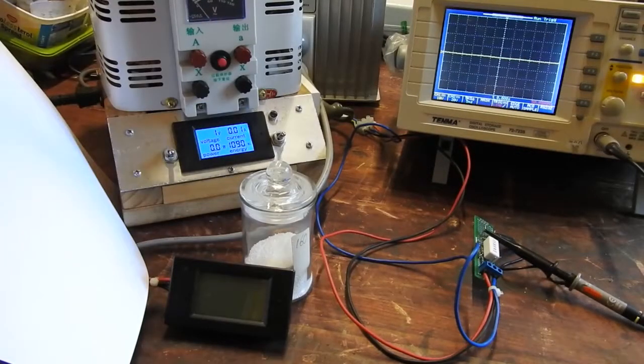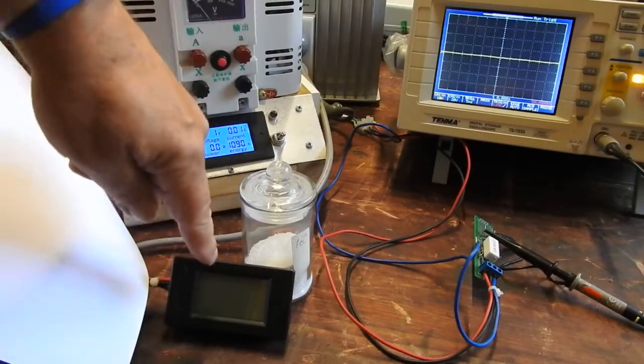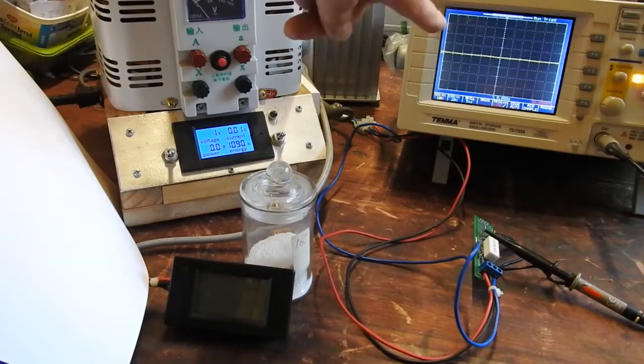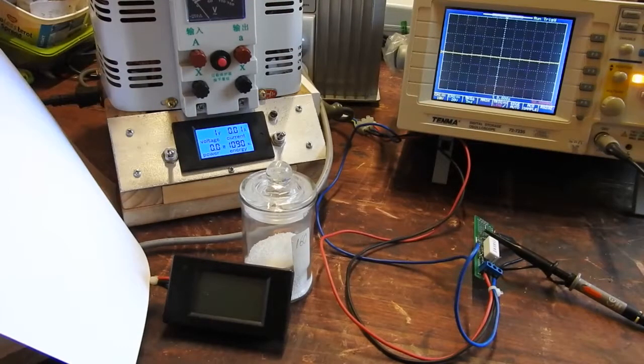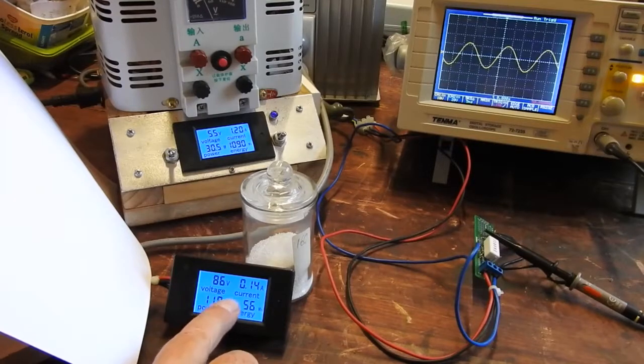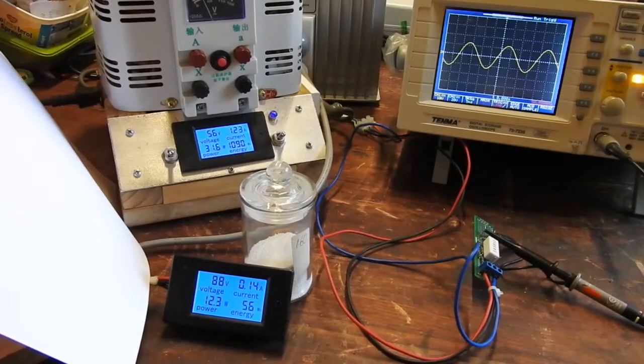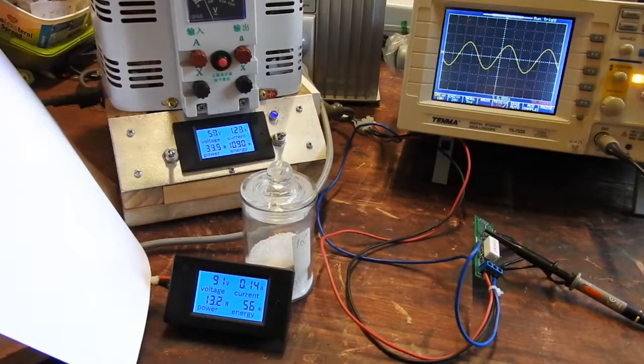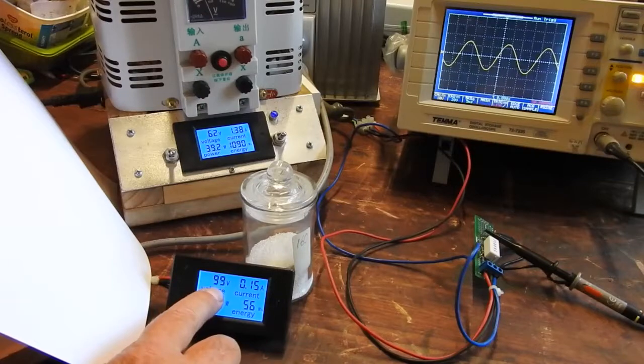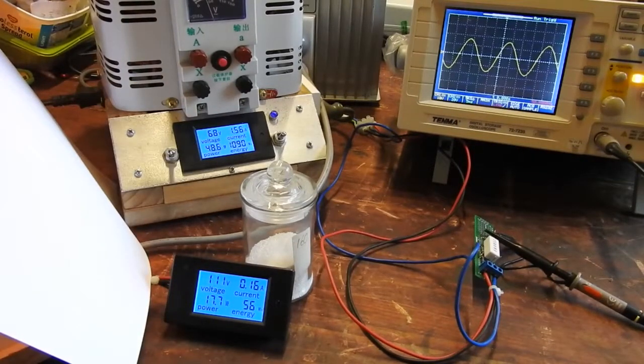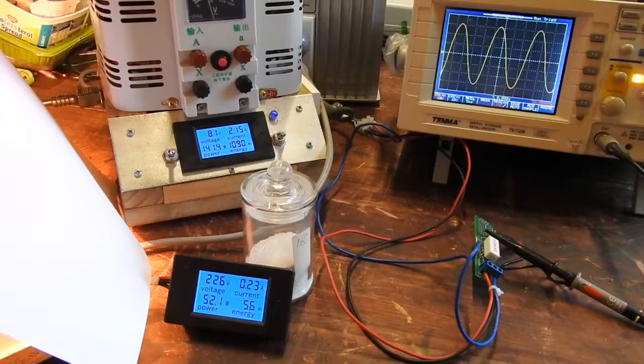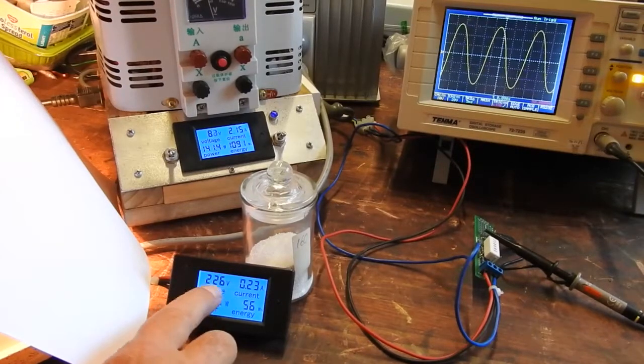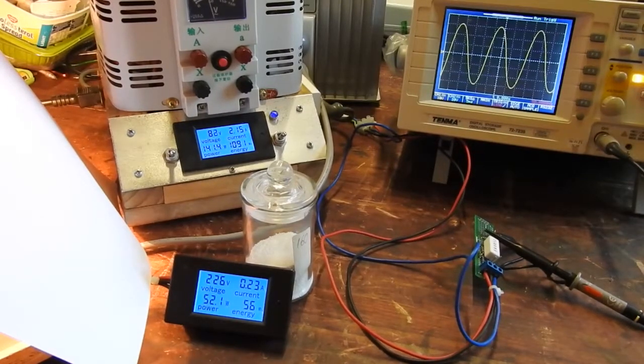Here we can see the incoming voltage to the Ferguson. Here's the output voltage on this meter and the waveform, and the dummy load globes are here behind that piece of paper to reduce the glare. Winding up the voltage, we're going to get at least 80 volts out before this meter starts working, so that's been met now. The globes are on dimly; we're only getting 100 odd volts out. When this gets to 80 volts input, around about here, suddenly the ferroresonant transformer is able to work with that 80 volts and go into its ferroresonant activity and give us a good mains output voltage of 226 volts.